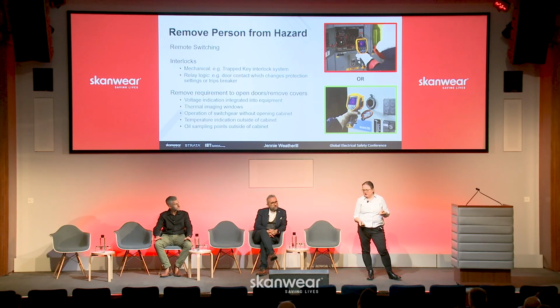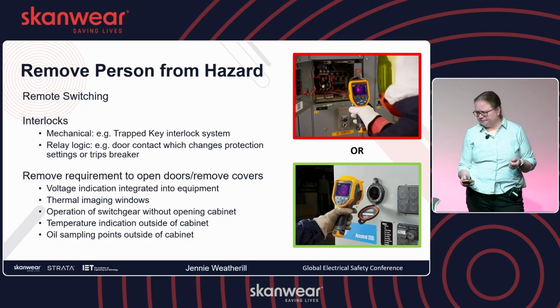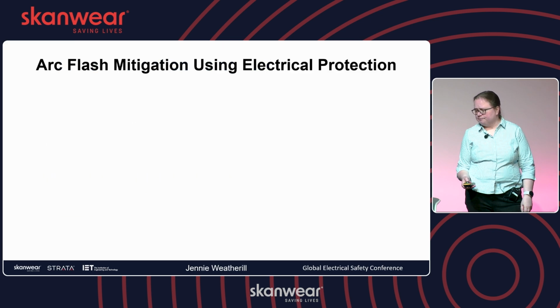Thermal imaging windows: we have retrofitted these on one of our sites, because the reason you're checking is that there's a risk of a fault, so you're asking the guy to stand there in front of it with a camera. If you can do it through a window and give him that protection, then that's well and good. Temperature indications outside, oil sampling outside of the cabinet. We've done this with small transformers, moving the oil tap for the DGA outside of the cabinet. You don't then have to open it and actually be next to that kit. So just some ideas. So, arc flash mitigation using electrical protection. We had some examples of it yesterday.